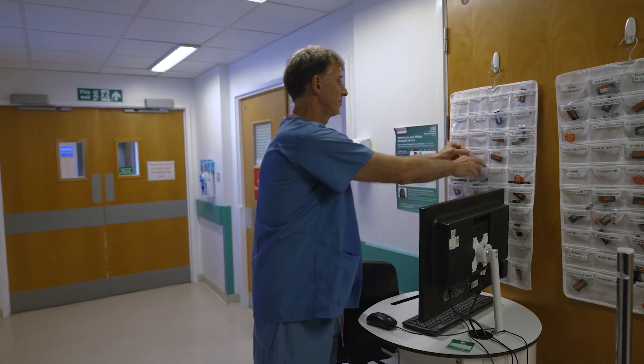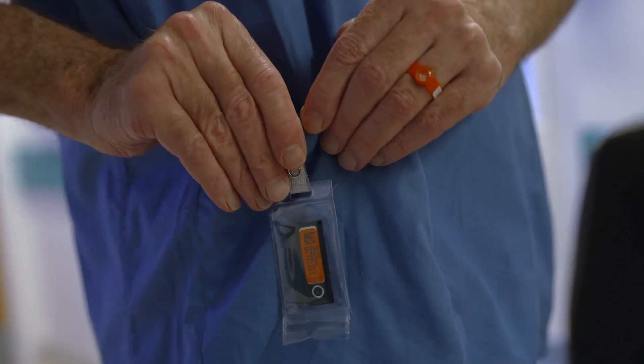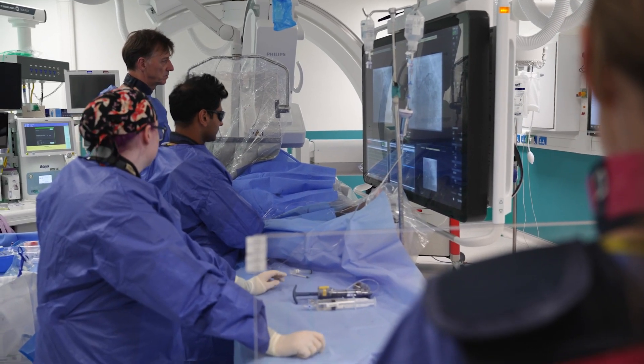Cardiologists wear protective glasses fitted with a dosimeter to monitor radiation dose to the eyes. Radiographers wear a whole-body dosimeter under their lead apron to monitor their career dose. Dosimeters are sent away regularly for testing to ensure nobody receives a harmful dose of radiation.